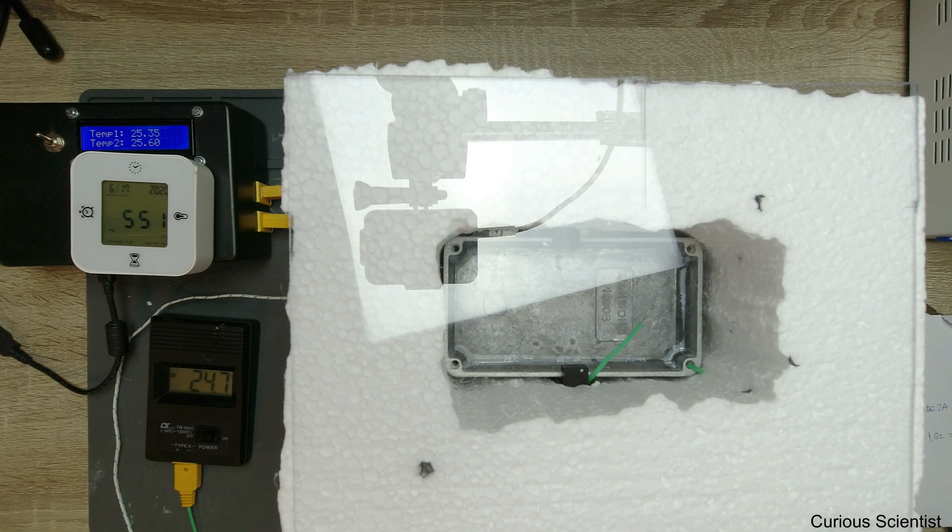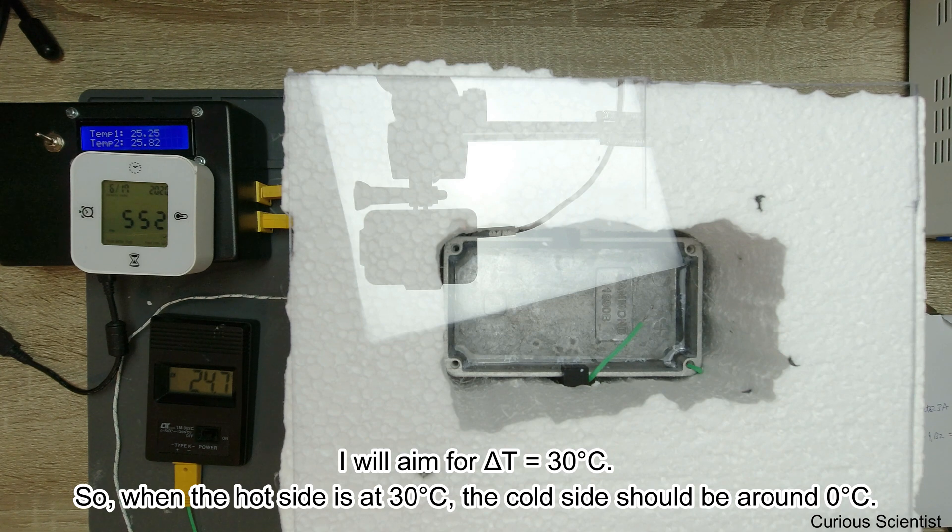So I did the same exercise here. We can see that we are roughly around 25 degrees. I overestimated this and said I would like to create 30 degrees delta T, so I want to go down to zero degrees Celsius.